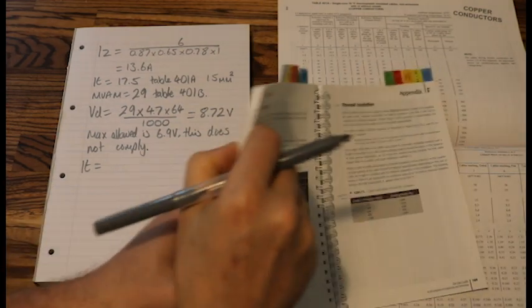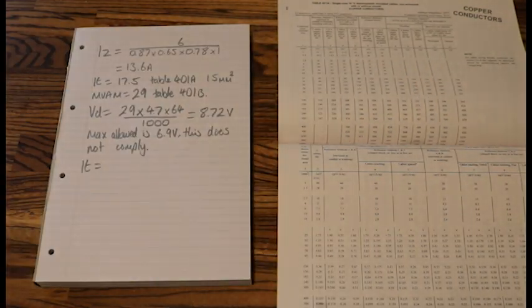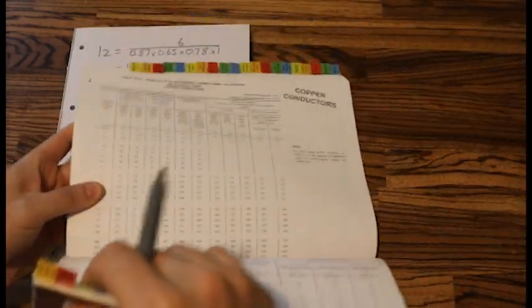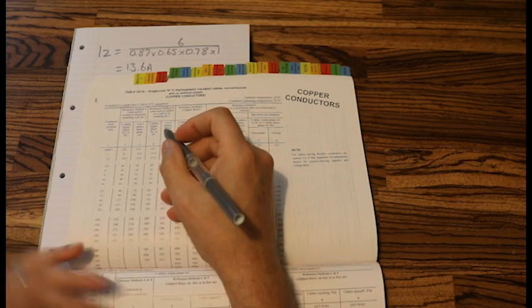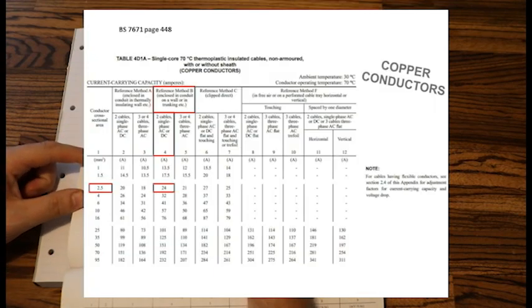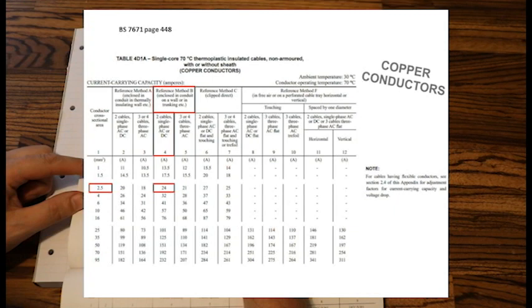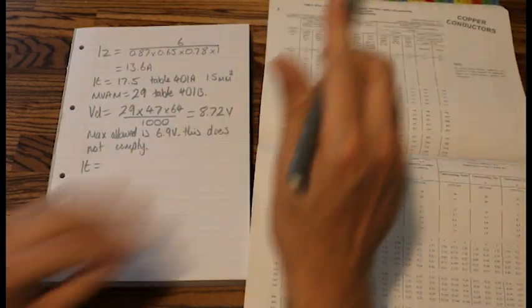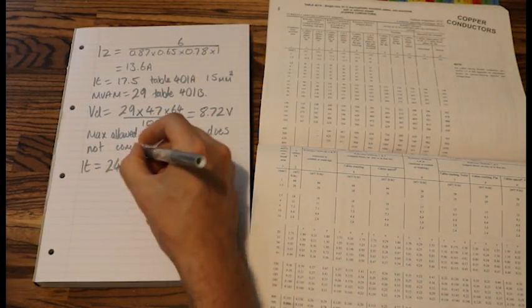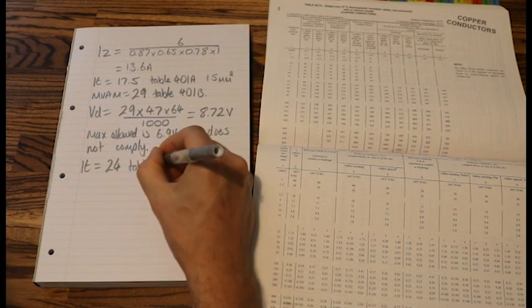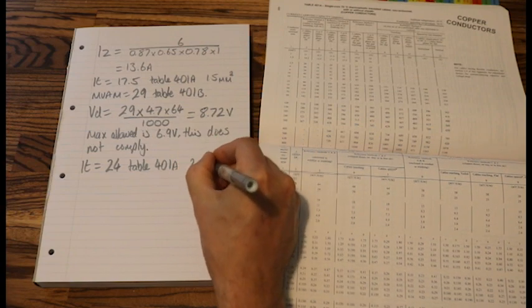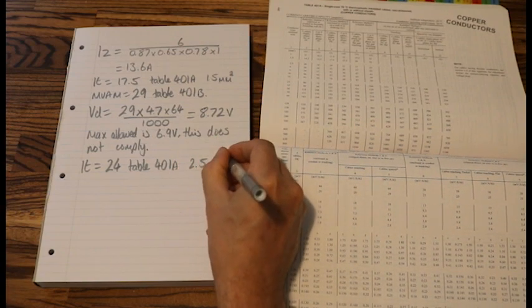So we go back to our IT. So we go back to our IT table, let's move the on-side down the way now. We go back to our IT table, and we go to the next cable up. So we were at 1.5 mil cable, so the next cable is 2.5, and my IT becomes 24. So we'll just jot that down, IT is 24, reference to table still 4D1A, 2.5mm cable.